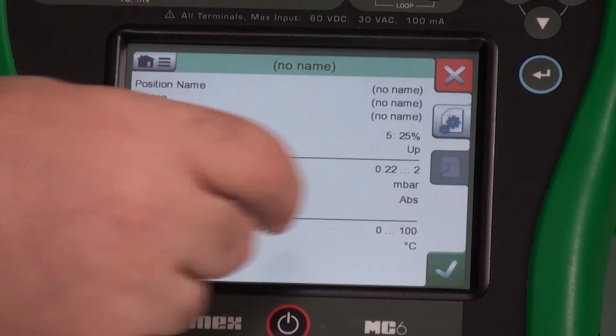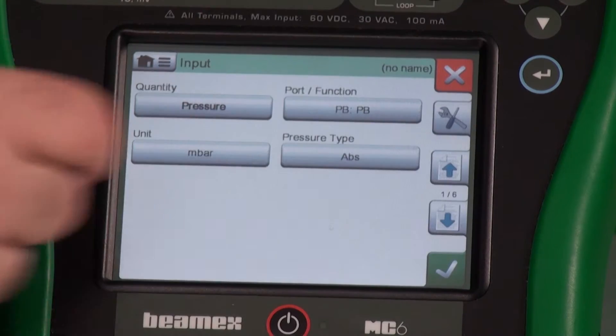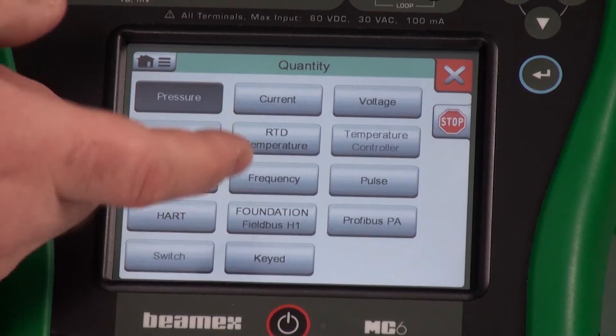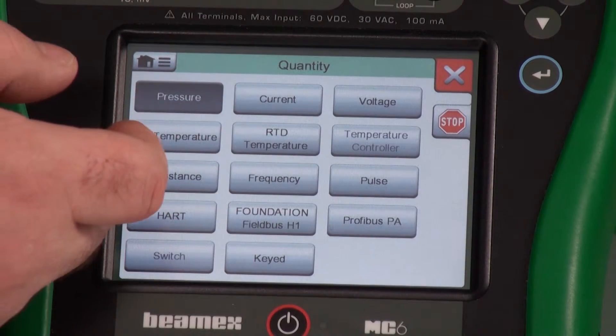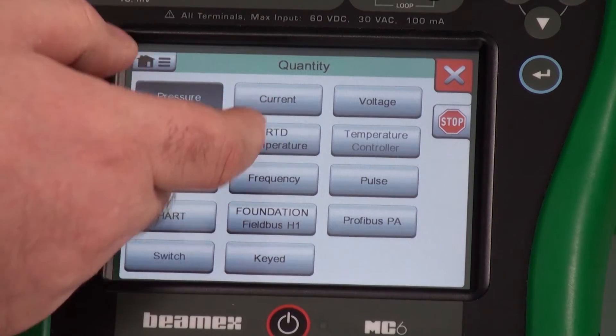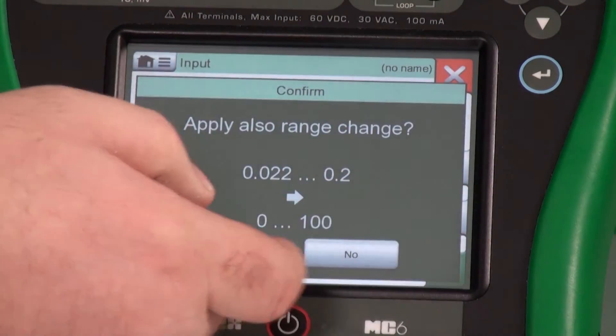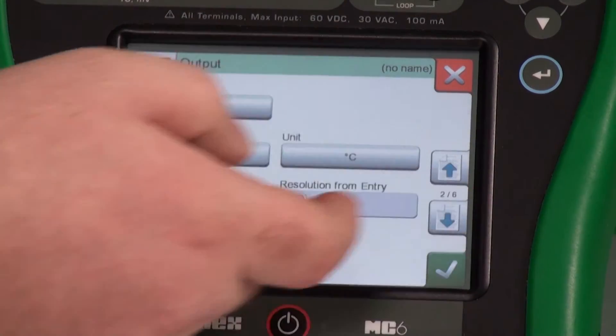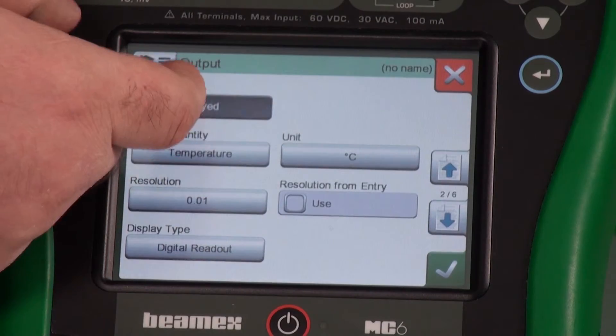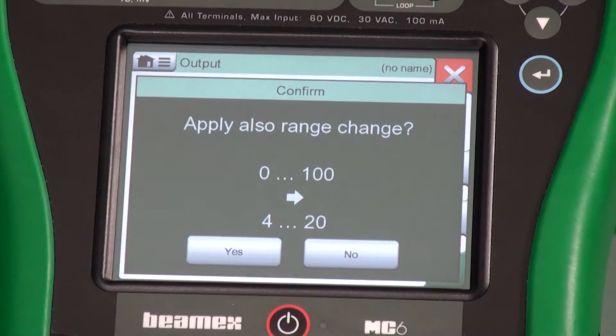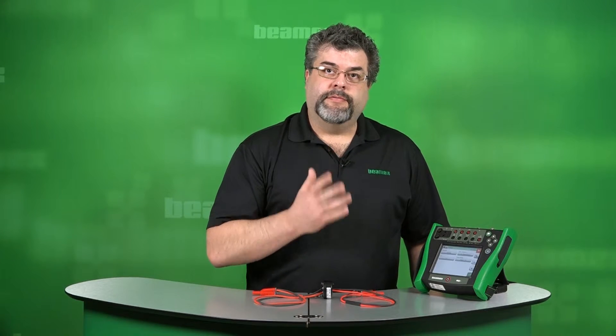So you're pumping up pressure — maybe you have the display in front of you, or maybe the display is in a control room and you're listening over the radio to get the value to punch in. But let's get back to my temperature transmitter. In this case, I want the quantity to be RTD temperature, and the output quantity will be current. We can specify each of the values and the parameters and punch those in.